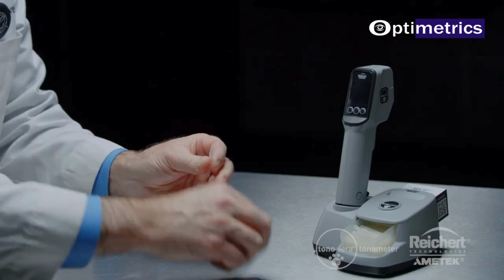You can rotate the device 360 degrees around the OcuDot probe and measure within a probe angle of plus or minus 15 degrees. To ensure that the probe is within the required range, there are probe angle indicators on the screen. The probe angle indicators will be yellow if the probe angle is too high or too low, and will be green when the probe angle is within the correct range. When properly positioned, the Tono-Vera Vet takes an IOP measurement automatically. The measurement dots will fill in as each measurement is taken. Reliable IOP results can be obtained in a single measurement, which reduces stress on pets.